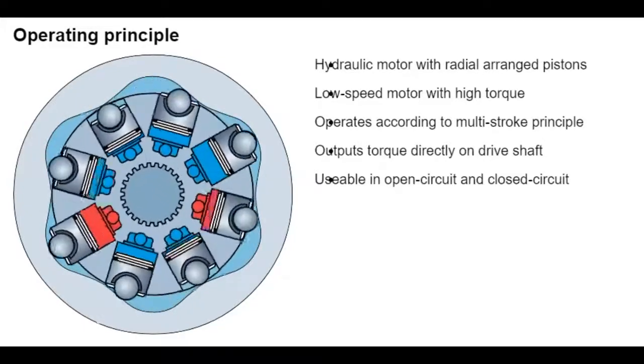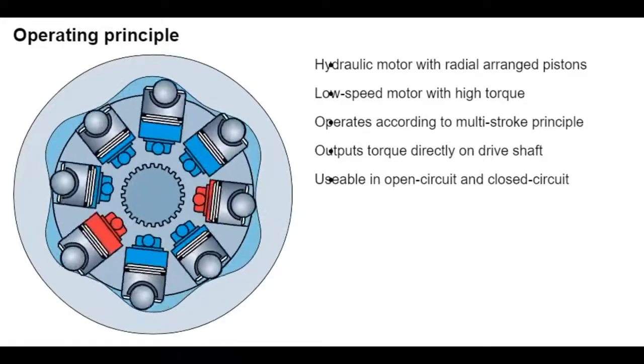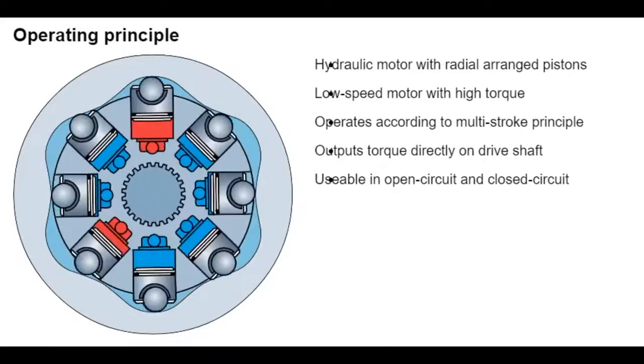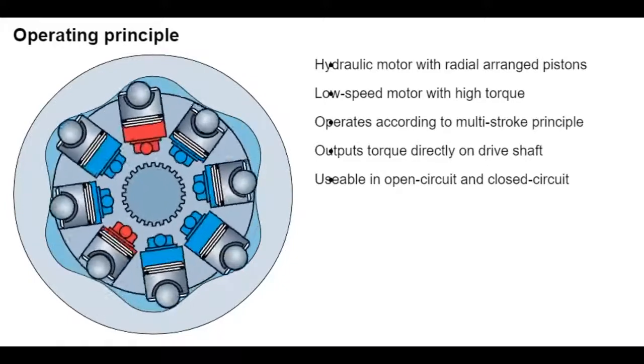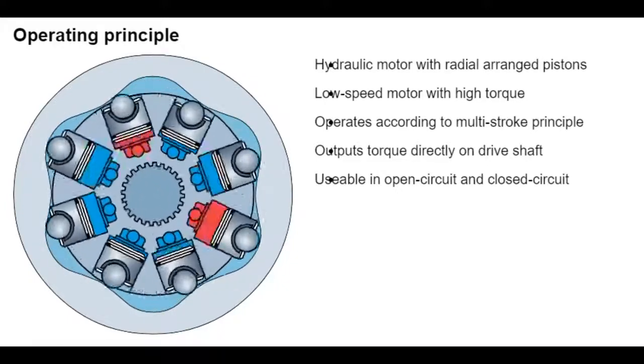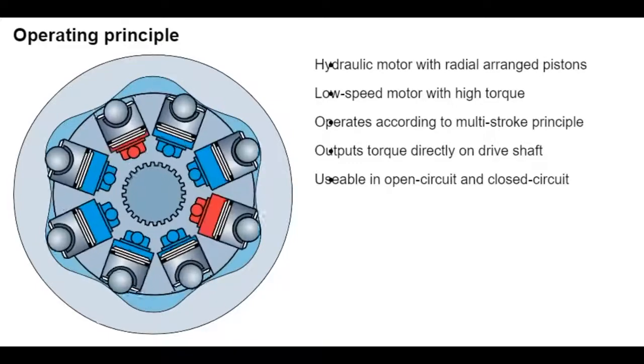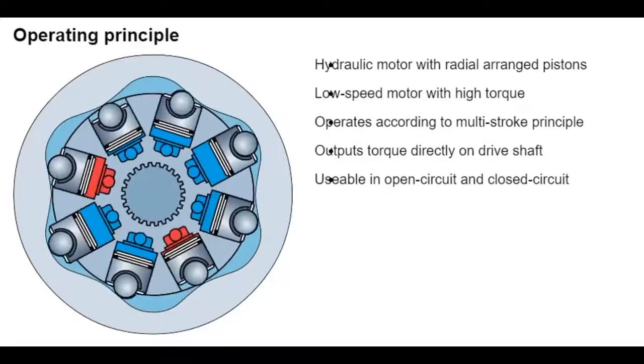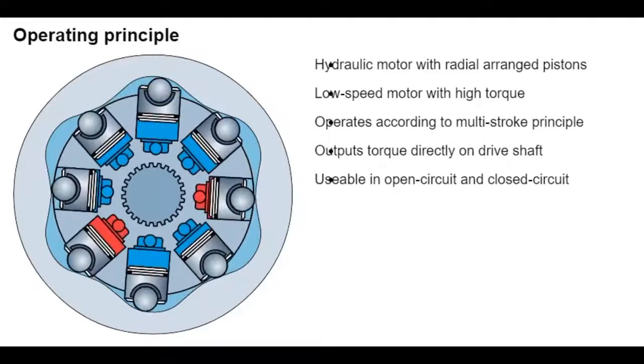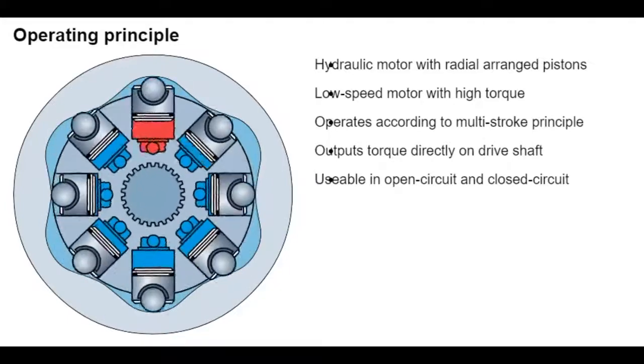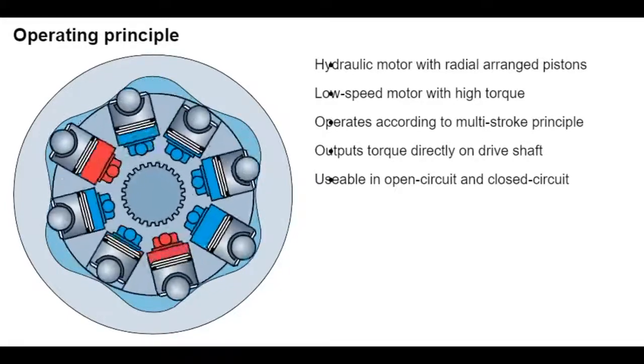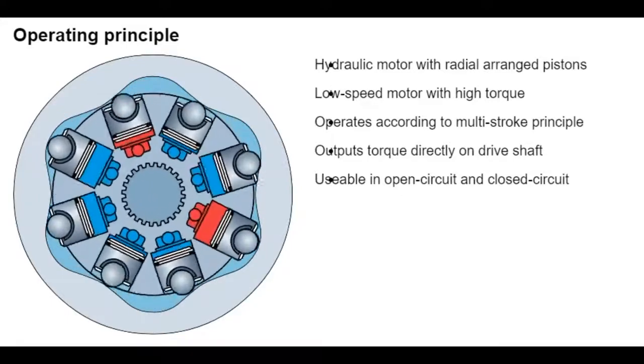Output torque is generated by the force caused by the pressure and the piston area. It grows with the pressure difference between the high-pressure side and the low-pressure side. Output speed depends on displacement and is proportional to the incoming flow. The number of working and return strokes corresponds to the number of times the cam ring is lifted, multiplied by the number of pistons.